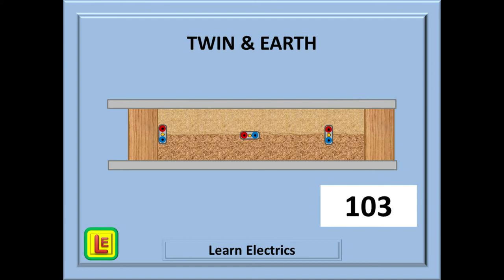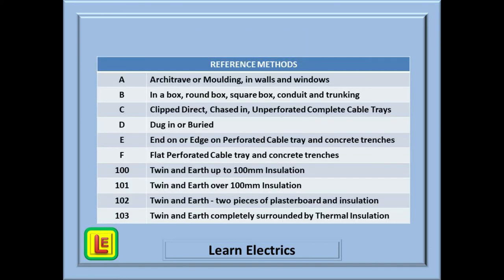They just lay the new insulation over the top of your cables, get a signature from the householder and move on to the next job. Your previously OK cable is now in an insulation sandwich. Now we are going to need a bigger number than the last. How about 103? So, cable completely surrounded by insulation is reference method 103.